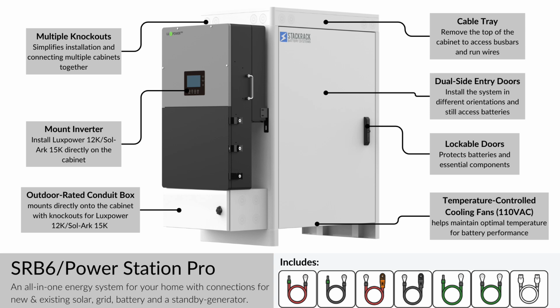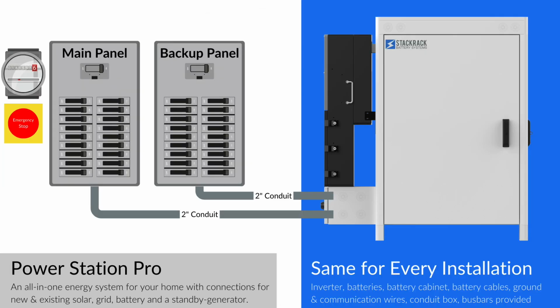The next cabinet is the SRB6 cabinet, which is our most popular cabinet. This cabinet was developed closely with our installation partners with the goal of reducing installation time and cost. This cabinet allows you to install a Luxpower 12K or Sol-Ark 15K directly on the side of the cabinet and make your battery connections through the included conduit box. And that means from an installation standpoint, this unit remains the same from customer to customer. The only difference being how long you're going to run conduit lines from the conduit box to the main panel or sub panel.